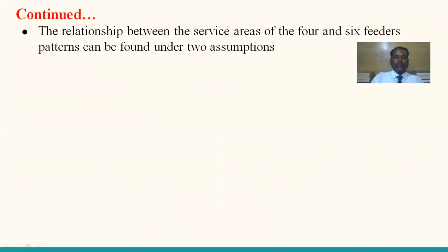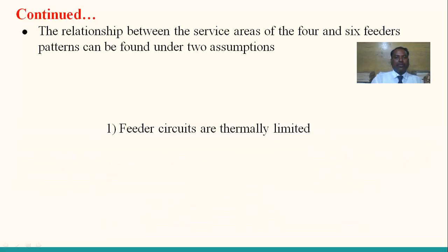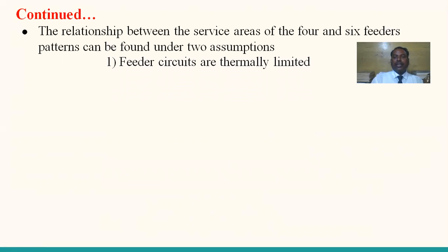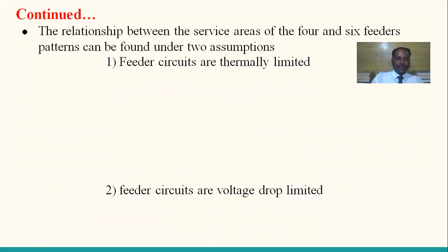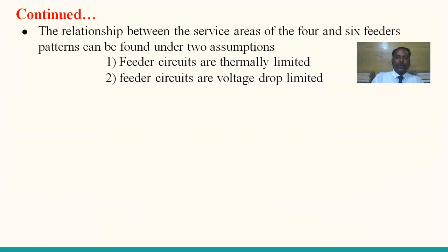The relationship between the service areas of the 4 and 6 feeder patterns can be found under two assumptions. Assumption number 1: feeder circuits are thermally limited. Assumption number 2: feeder circuits are voltage drop limited. By using these two assumptions, we compare the 4 feeder and 6 feeder patterns. Let us see the first one, feeder circuits are thermally limited.